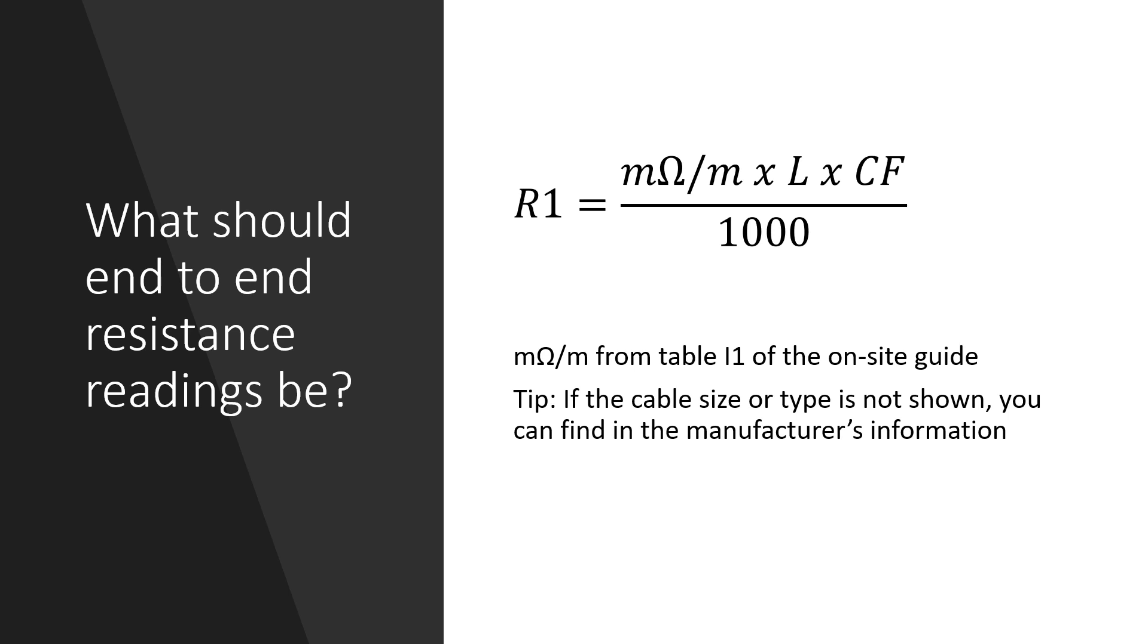So to work out what to expect the end-to-end readings to be we take the value for the size of conductor and calculate as follows: milliohms per meter multiplied by length multiplied by correction factor and then divided by 1000.